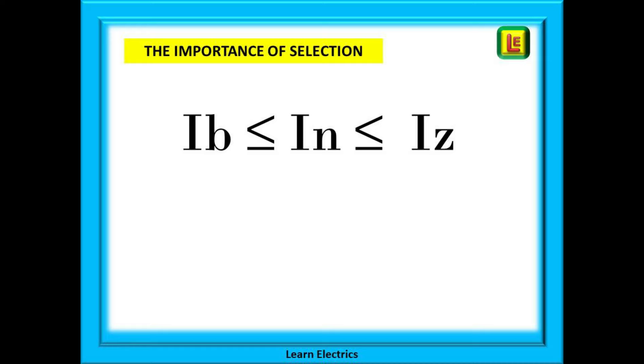We are sometimes asked why it is important to make the correct choices. Well there are two basic reasons. The circuit breaker must be the right size to carry the load but not so big that it never trips, and the cable must be able to carry safely any overload current until the breaker operates. This principle is shown in the equation on this page.